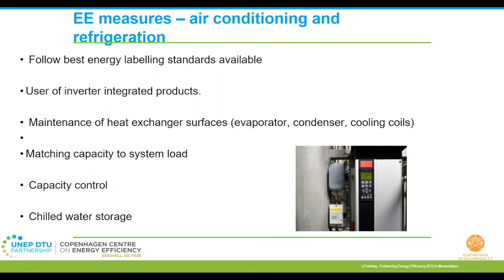Basically, you cannot actually have constant cooling loads or heating loads throughout the year, right? There's always some variation. So if the variation is way too high, then it is important that you have capacity controls in place.